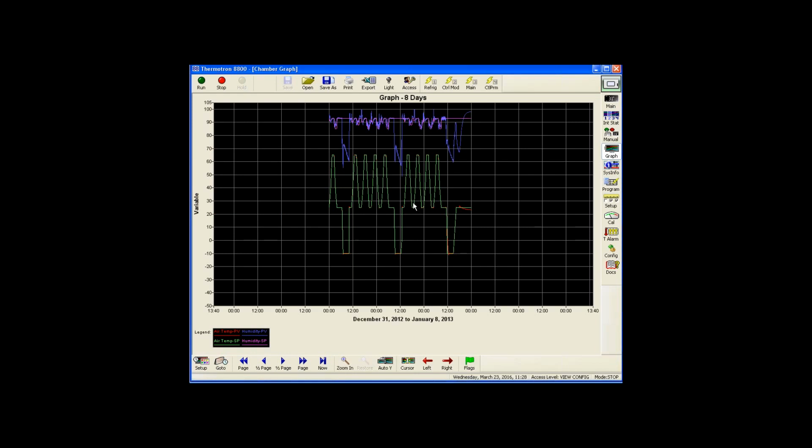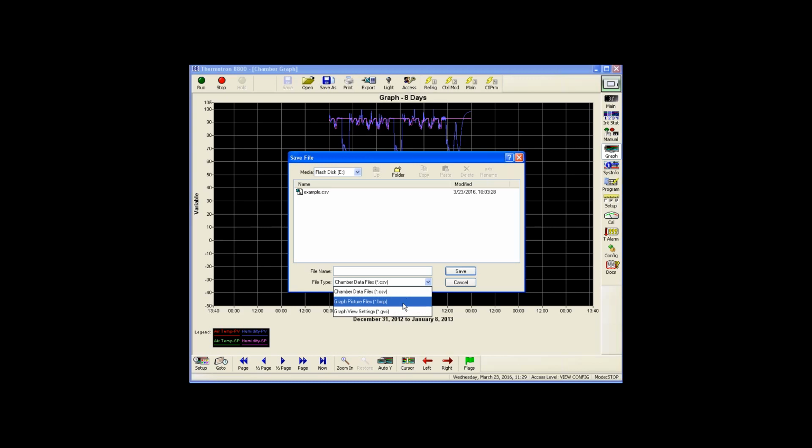One of the other things I wanted to expand on a little bit is just some of the options we have for saving data. And again, to access the graph or paperless recorder, you just select the graph icon. It'll pull up your test data. This is always saved on the hard drive. You can turn on different channels, different sets of data, and display it the way you want to import into a test report. And I'll show you the few different ways of doing that. So first way is we can save this as a bitmap, which is just a picture.